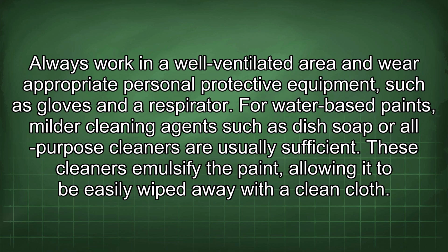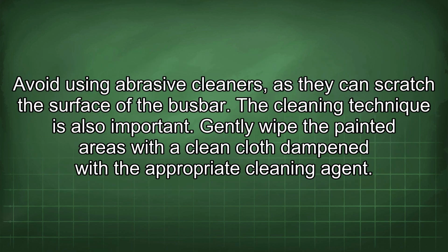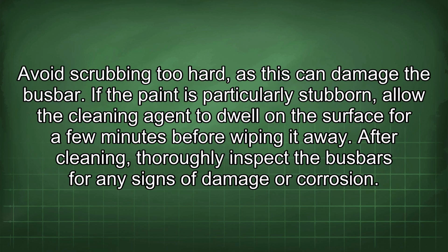For water-based paints, milder cleaning agents such as dish soap or all-purpose cleaners are usually sufficient. These cleaners emulsify the paint, allowing it to be easily wiped away with a clean cloth. Avoid using abrasive cleaners as they can scratch the surface of the busbar. The cleaning technique is also important. Gently wipe the painted areas with a clean cloth dampened with the appropriate cleaning agent. Avoid scrubbing too hard, as this can damage the busbar.